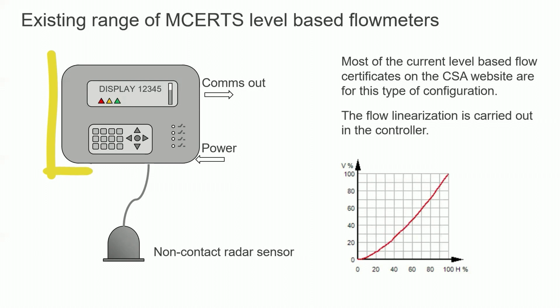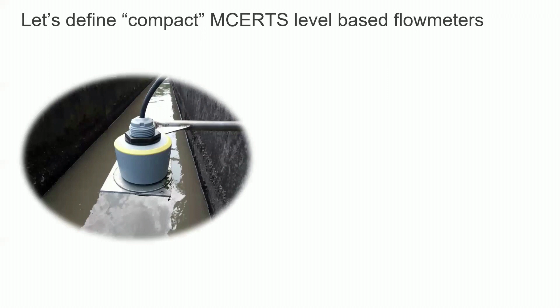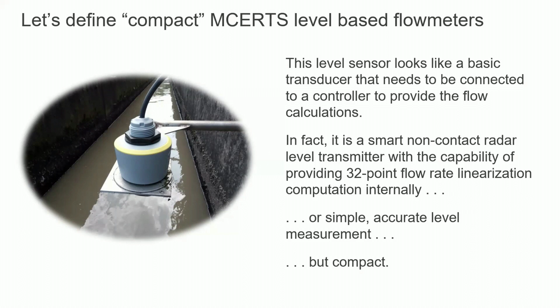We're talking about compact devices. So let's define what we mean by a compact MCERTs level-based flow meter. If you look at this photograph, we can see what looks like a very basic level transducer that needs to be connected to a controller to provide the flow calculations. In fact, this is a smart non-contact radar level transmitter with the capability of providing 32-point flow rate linearization computation internally inside that sensor. Or simple, accurate level measurement, but compact. It does not require a controller. In addition to the linearization for flow, it can provide HART diagnostics, including parameters such as measurement reliability.